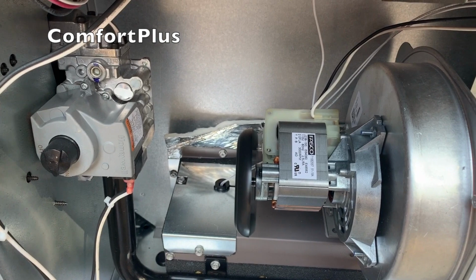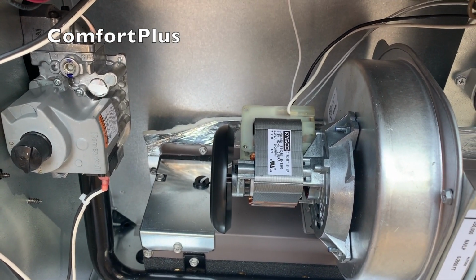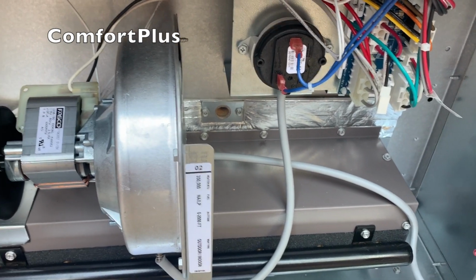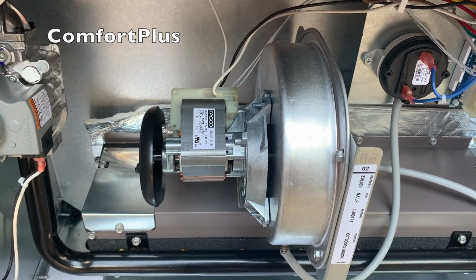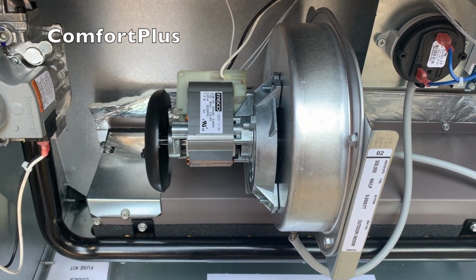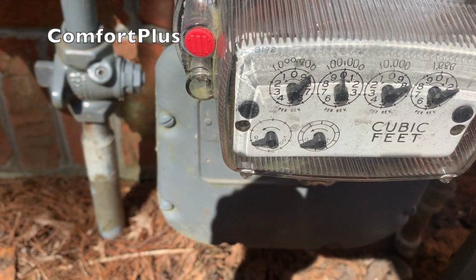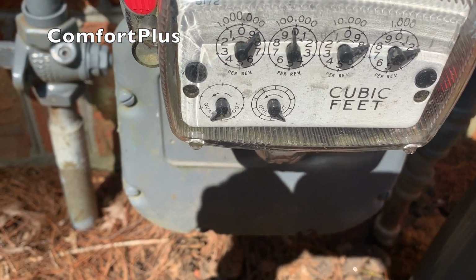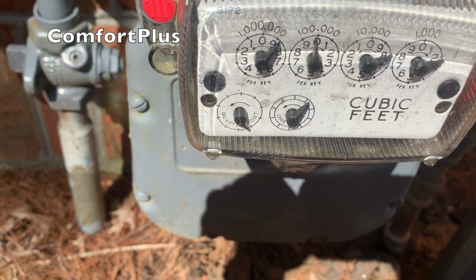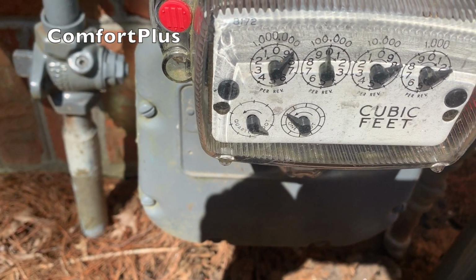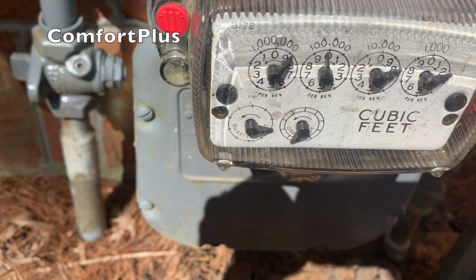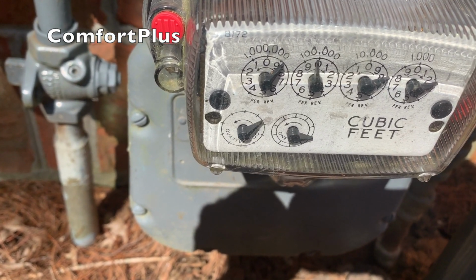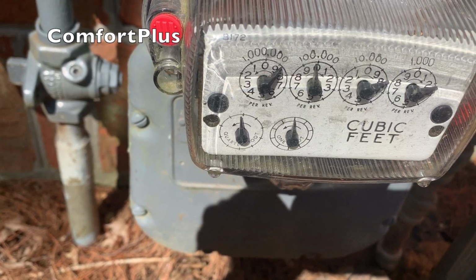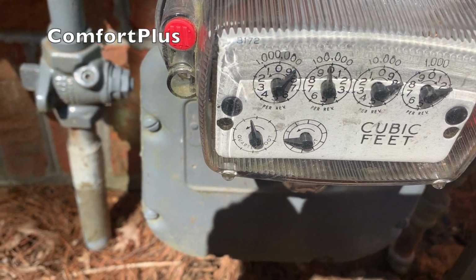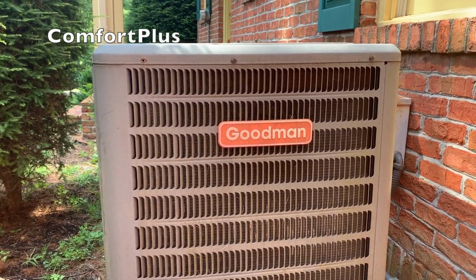Okay guys, she's up and running. Pretty loud, of course. Anytime you have a burner burning 350,000 BTUs, it's going to be loud. I went out and clocked it at the gas meter. I'll show you that. Watch that baby go. Of course, that's the quarter cubic foot scale, and there's the 1 cubic foot scale. I just clocked it using the iManifold app, and it was 353,000 BTU, so it's pretty close. You can't clock these things perfectly because those little meters get little hitches in them from time to time. That's what's making all the noise.